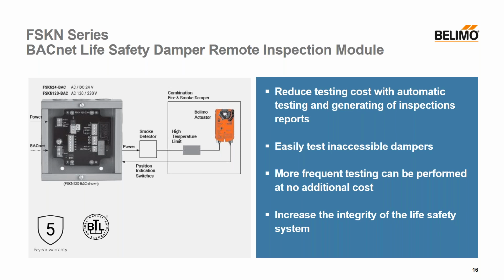The fire alarm and BAS companies will be more efficient with testing dampers and comply with code requirements, ensuring proper damper operation. Inaccessible dampers can be inspected. Deferred testing and maintenance will be reduced with automatic testing and generating of inspection reports. System commissioning can be more carefully performed. Instead of every 4 or 6 years, frequent testing can be performed at no additional cost. Overall, the integrity of life safety will increase. And you can find this information at the end of the fire and smoke section, behind page 3-3.